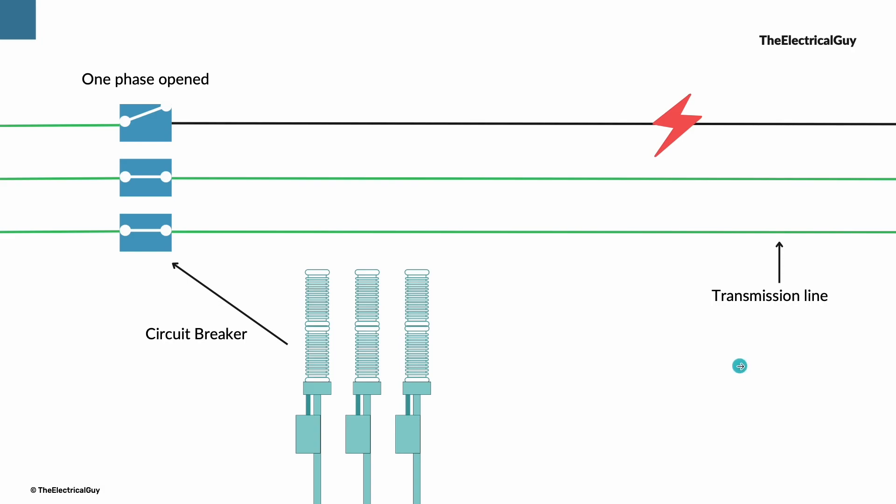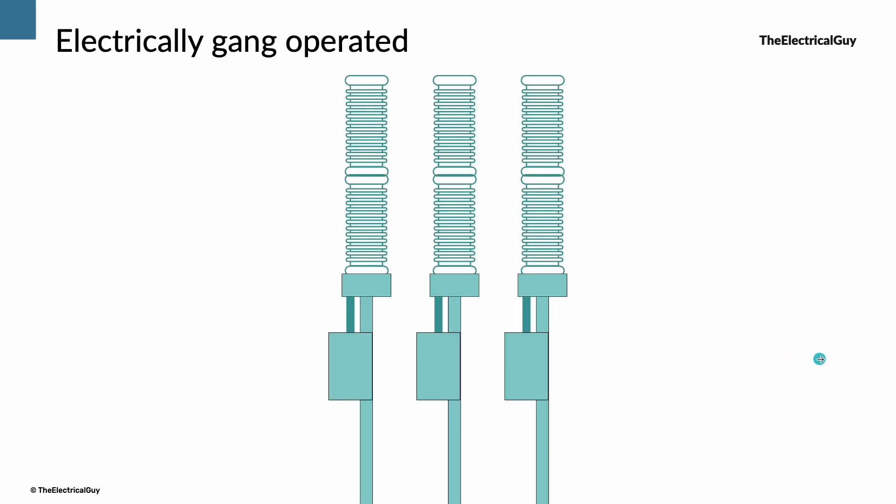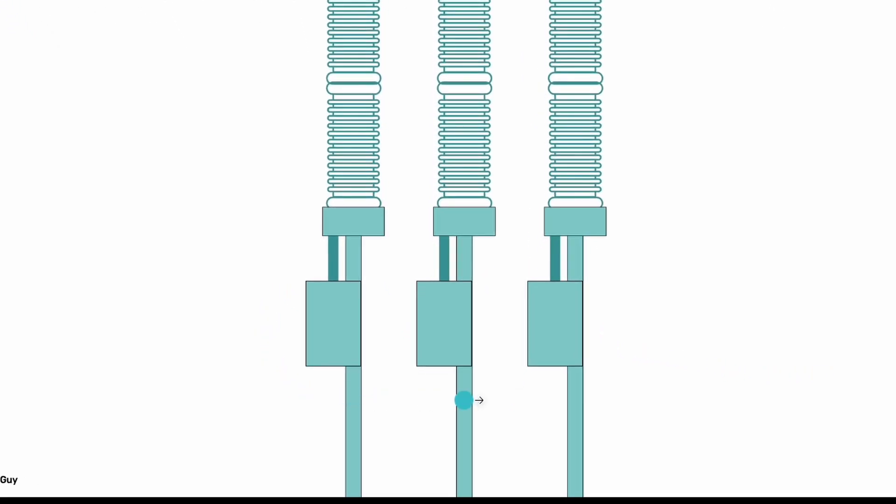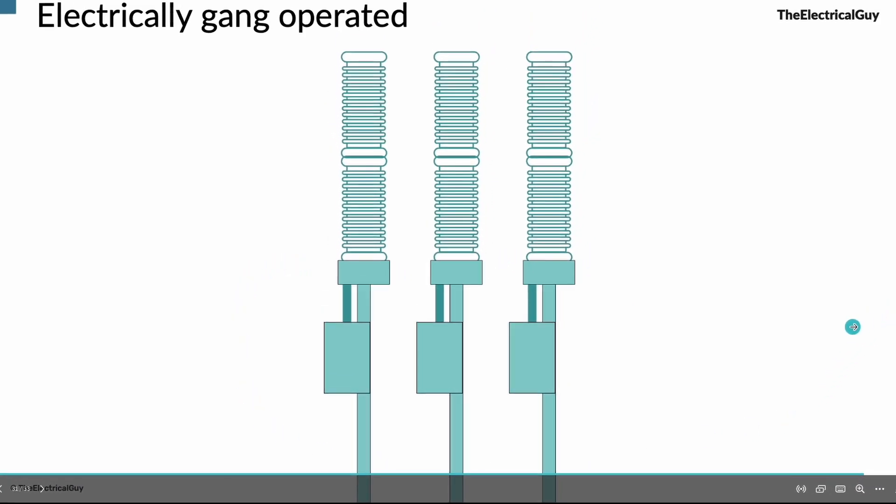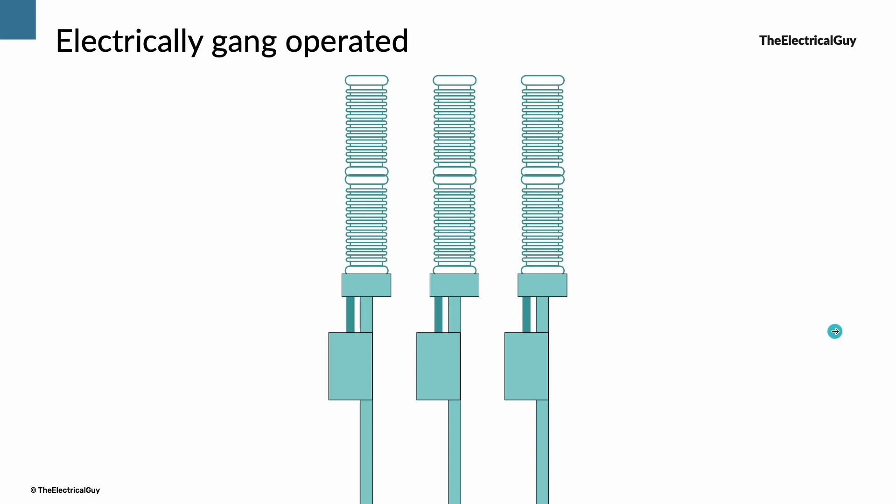But it is important to note that single phase auto reclosing can only be performed by an electrically gang operated circuit breaker. That means every phase of circuit breaker will have its own dedicated mechanism. In that case only, a circuit breaker will be able to trip or close one phase out of three.